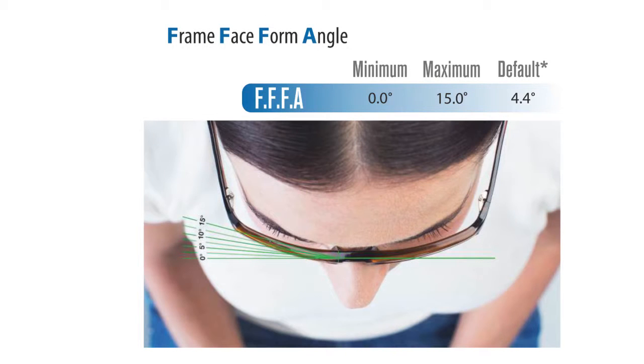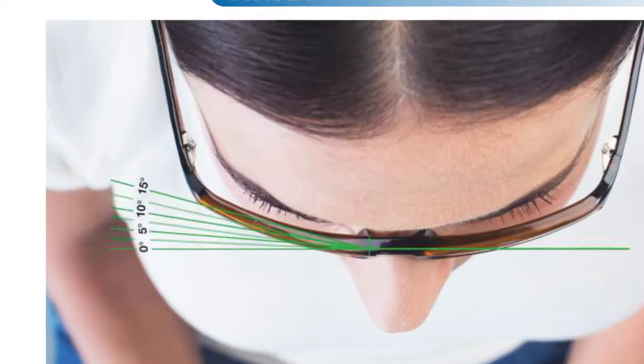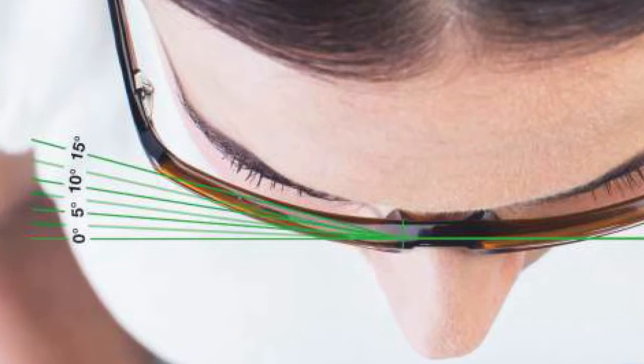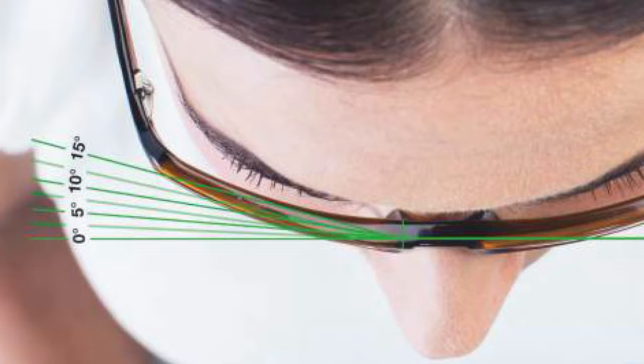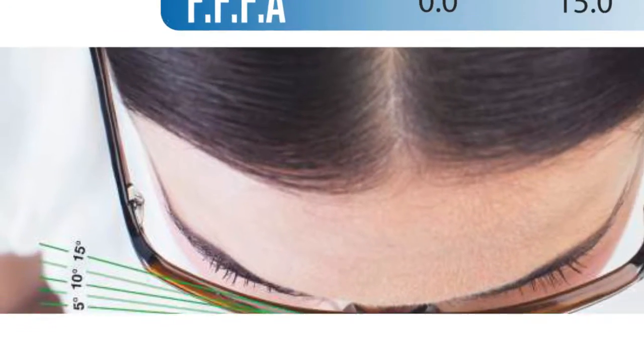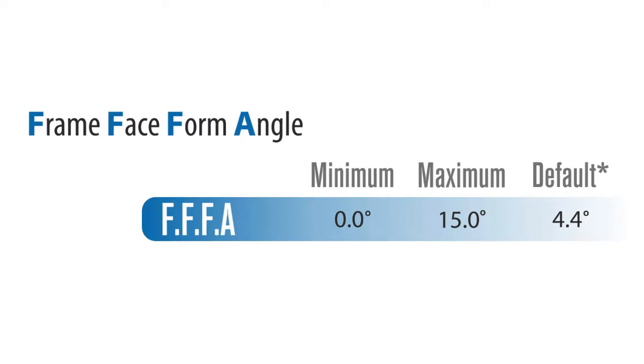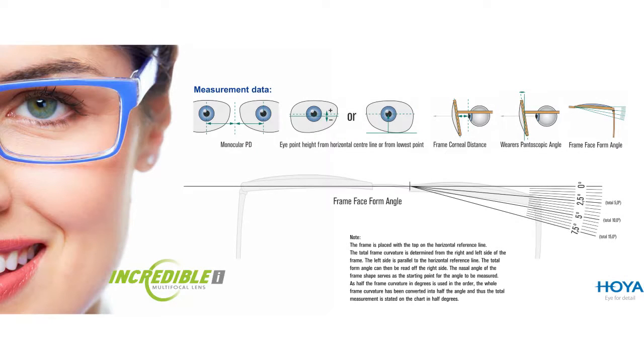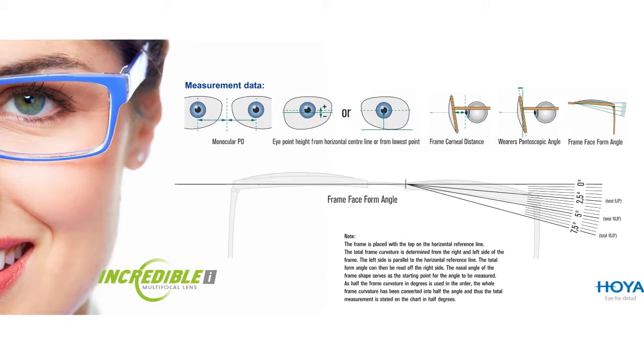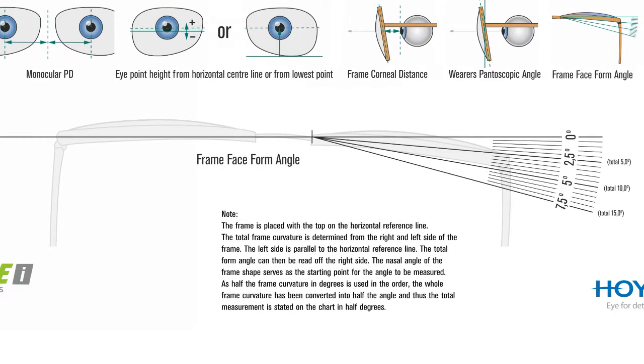The last parameter we are looking at is the frame face form angle. Let's define it as the angle where the frame would wrap the face or where the frame is slightly curved instead of being perfectly flat. The default value being 4.4 degrees with a minimum of zero degrees and a maximum of 15. To measure the frame face form angle, we will provide you with a chart such as this. You will literally just place the frame on the chart and read off the frame face form angle on the protractor to the right.